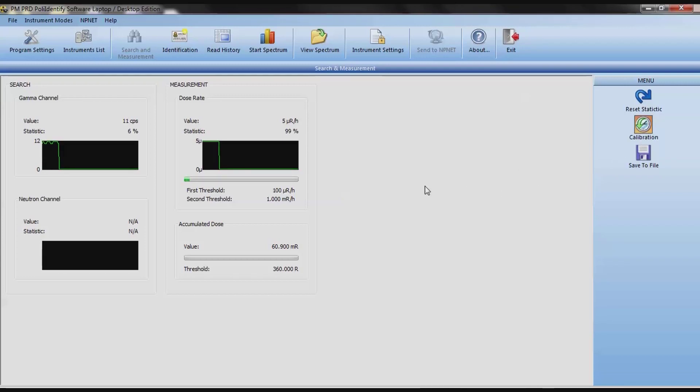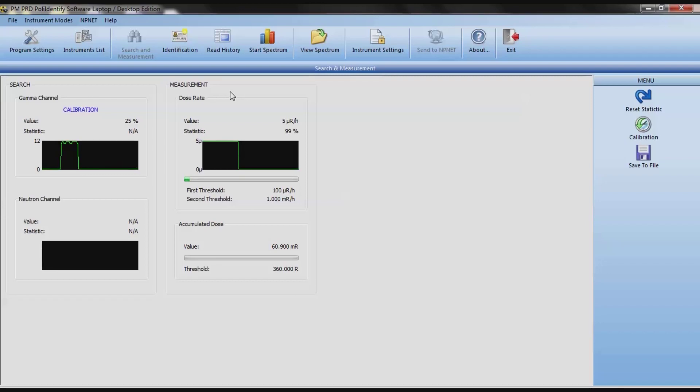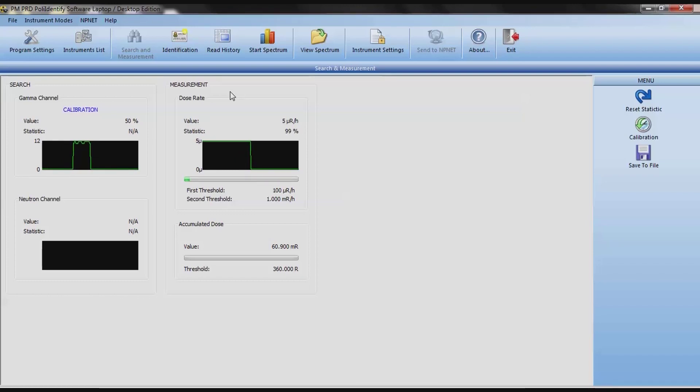Now, let's calibrate it. We've moved the box away. You move the package away from the unit. In fact, you should probably do this before you even start running packages past it or testing anything for that matter. Calibration is a good way to get the unit nice and squared away and set and ready to go, and also make sure it's aware of the current background temperature, which is very important when doing gamma spectroscopy. And even if you're doing just the rapid isotope detection feature and you're not actually doing gamma spectroscopy, just the push button version of it, it's still important to make sure you do this. Click the calibration button, let the unit calibrate, give it a minute. Don't move it around while it's calibrating either. It does take it a few seconds to do.